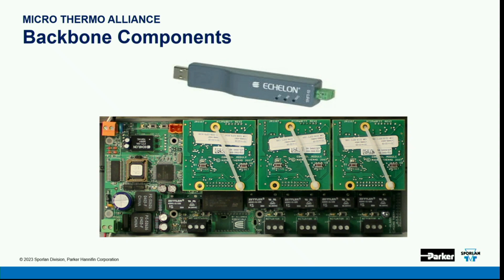And what we've done with all of the new nodes is we only have the ability to have one network connection. We do that for a reason. You twist both blacks together, you twist both whites together, that bonds the Echelon channel, and even if the node gets fried or you unplug it, you are not going to take the rest of the network down.